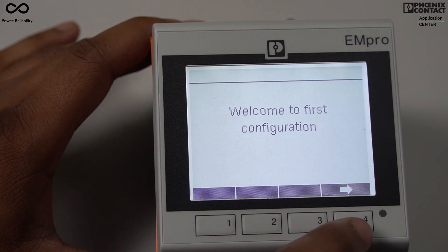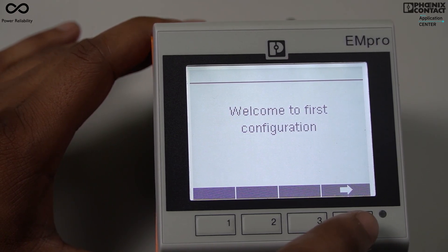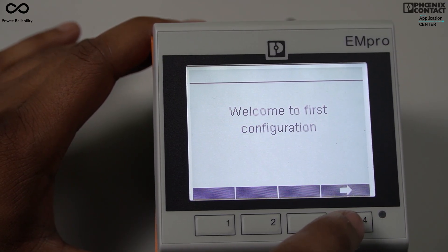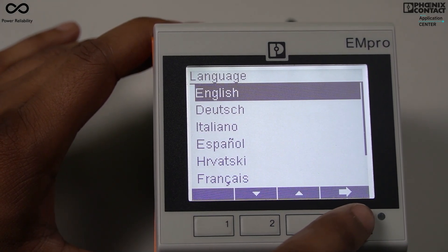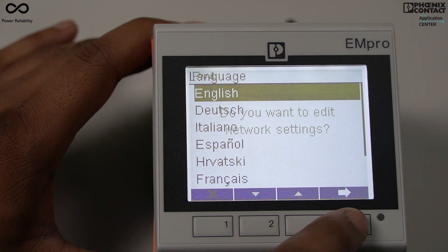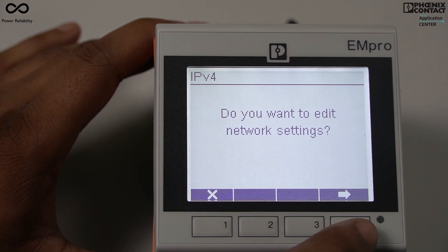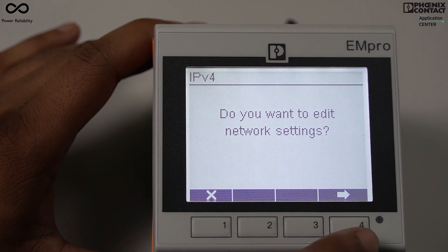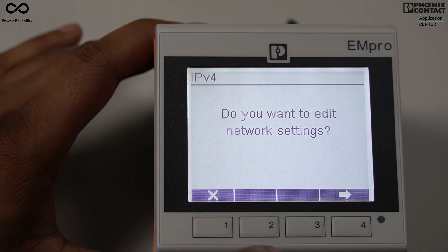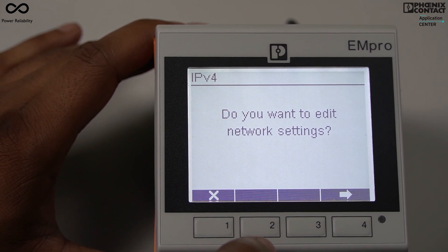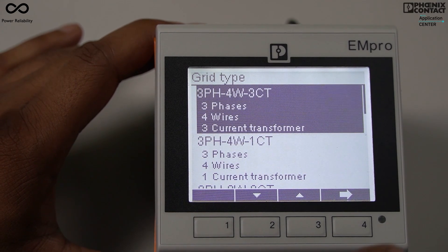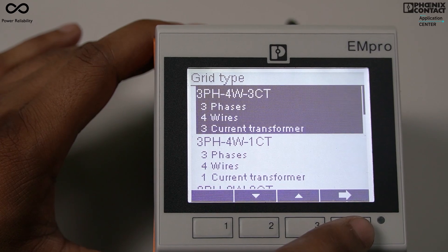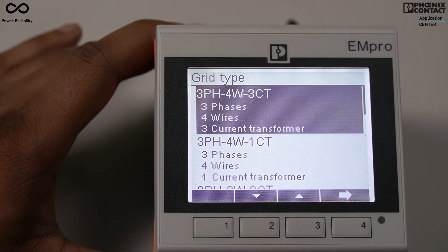When you first switch on the EMpro, it will show 'Welcome to First Configuration.' Press the key and language selection appears — I am selecting English. It then asks if you want to edit network settings, but we are not going to edit those. We will edit the CT ratio and PT ratio in this video. Now it is asking for grid selection, so I am selecting three-phase, four-wire, three current transformer as my grid selection.